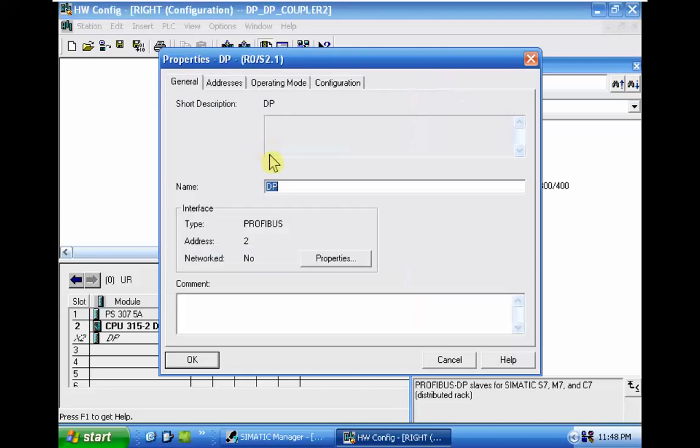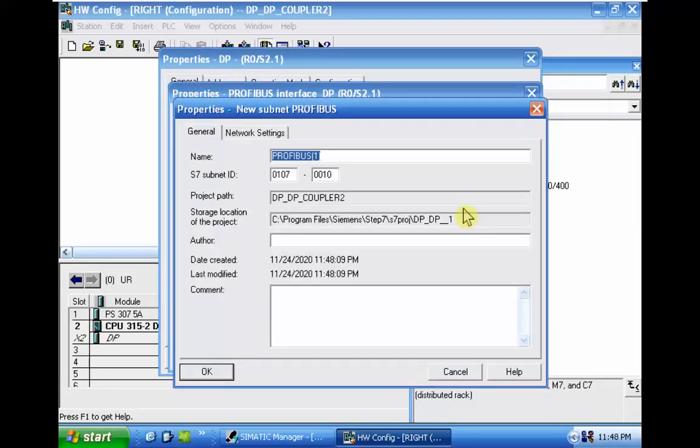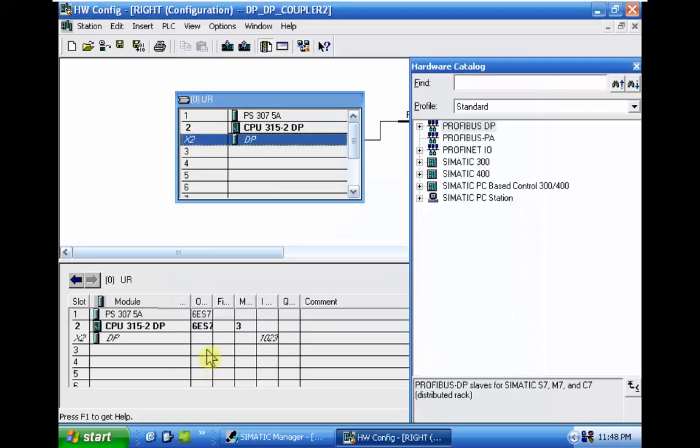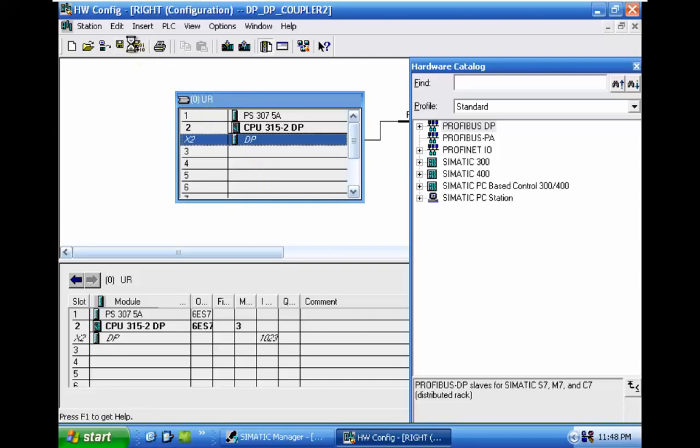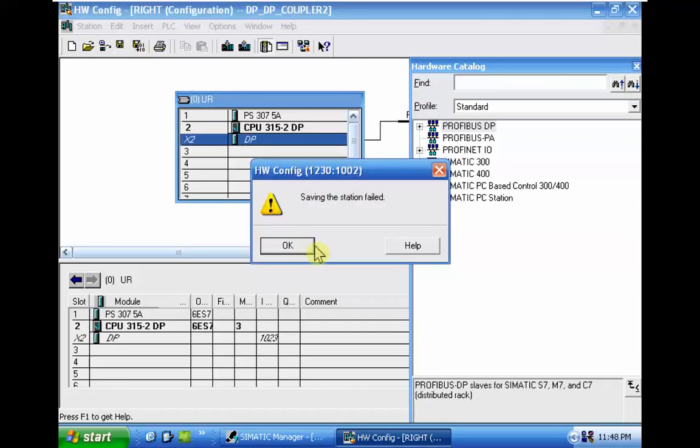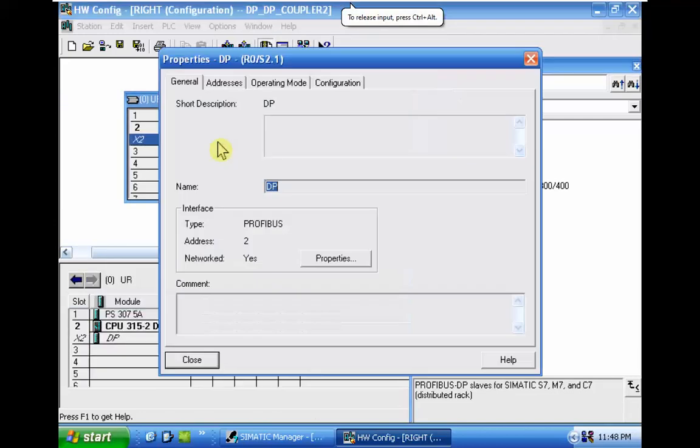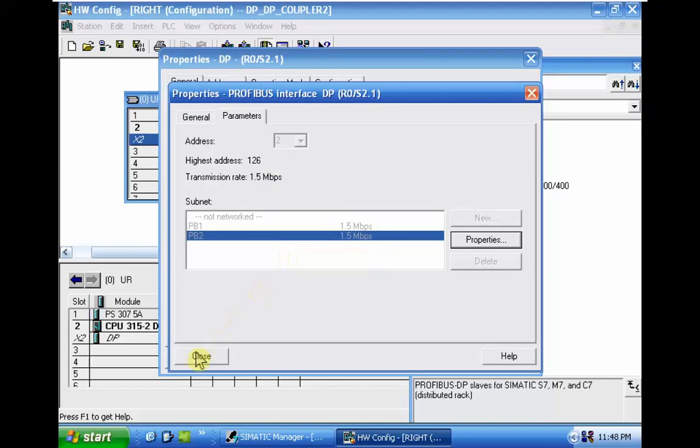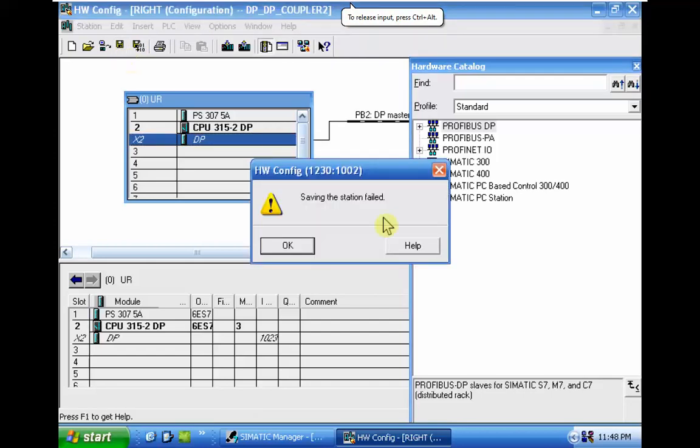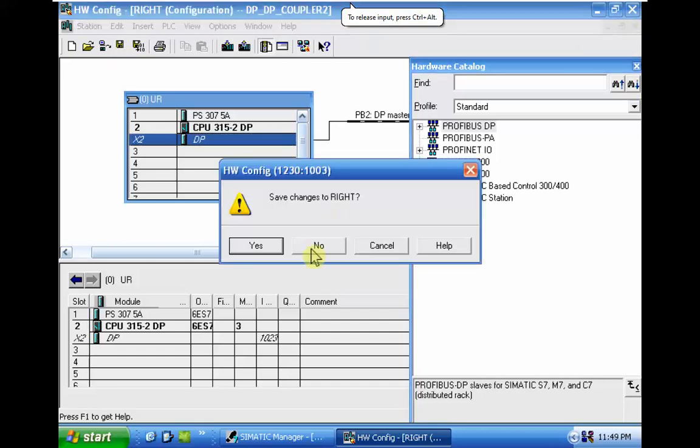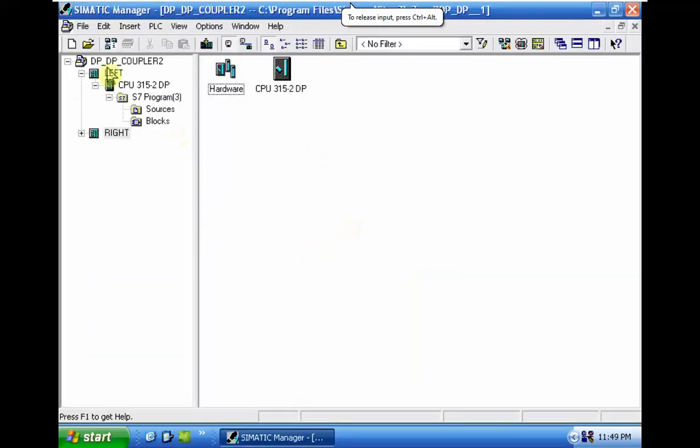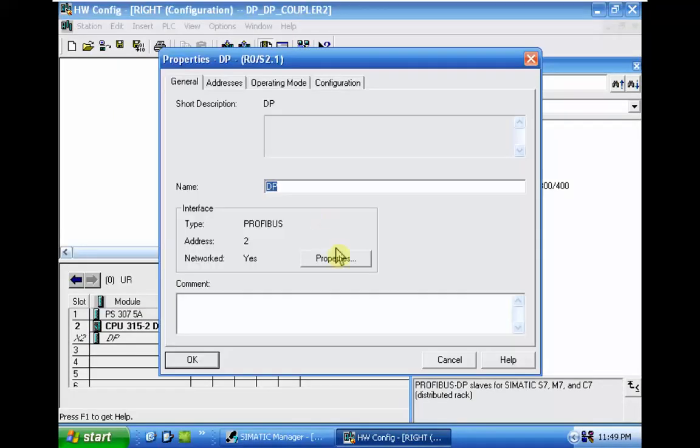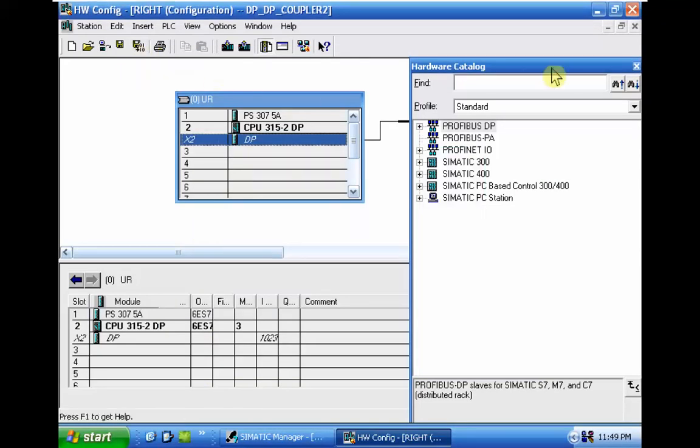In the DP we should create a new DP network because in DP-DP coupler we should have two Profibus DP networks with different physical media, different baud rate and everything. So we have two different DP networks. Let me close the DP master. Now let me check again the PB2. We are PB2 and now it's possible to save and compile.